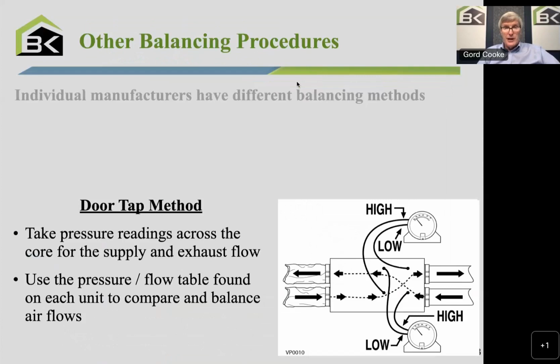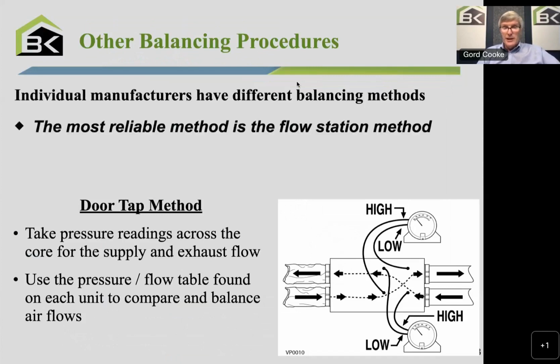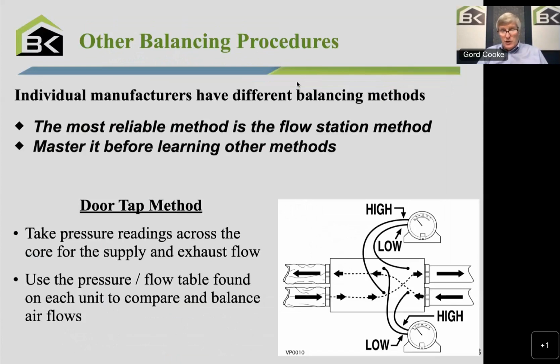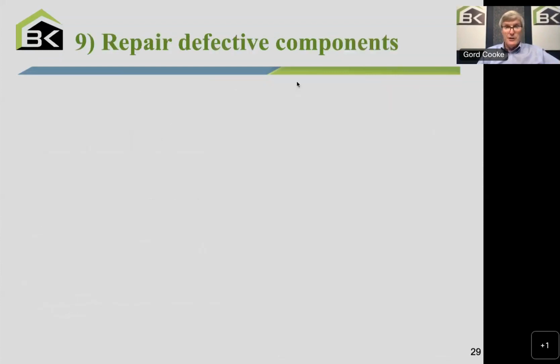And then, of interest perhaps, many manufacturers now have these new balancing methods. While I would always say that the flow station's the most reliable, there are manufacturers who have balancing taps built into the unit itself. You'll see 4 little plugs on the door of the unit down at the bottom right there. That's the place where I plug in the hoses from my gauge. You're seeing the 2 gauges there, and you can actually measure the flow right on the unit. Now, each unit comes with a little balancing calibration chart, so you have to look on the chart and figure out what the airflow is. Again, I don't want to go too deeply on this today, just wanted to mention there are different methodologies that are used.